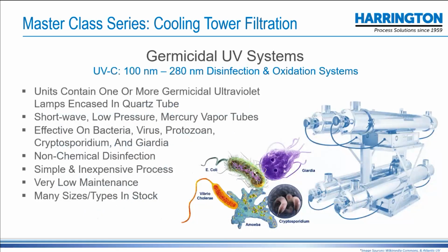And the last one is germicidal UV systems. If you have an open loop HVAC system, and the CDC requires at least annual testing for bacterial levels, and you're still concerned about the Legionella bacteria, or for that matter, any of the other bad guys, well, you can go ahead and run a UV system as a post-treat. The UV system really only applies if you do have an open loop HVAC type system where people are going to perhaps be breathing in some vapor, but you can sanitize it completely with this.